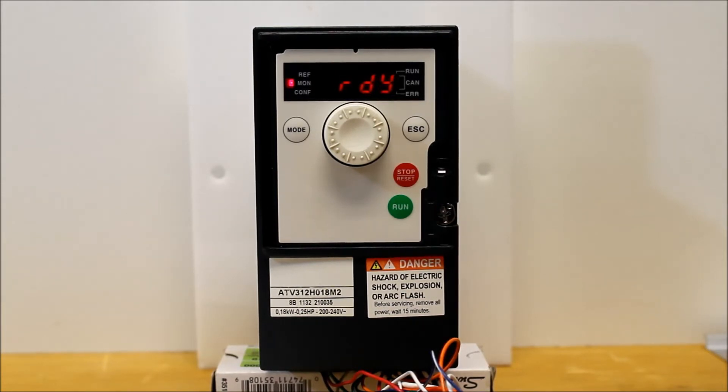The external fault is basically a permissive or safety function where in the event that a logic input gets a 24 DC signal on the corresponding logic that you program it to, it will fault out the drive on an external fault.